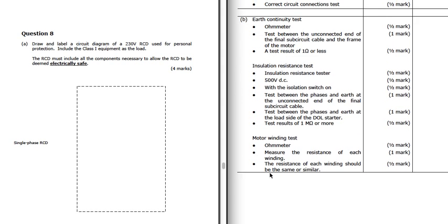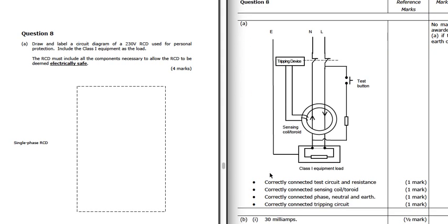Question 8, we're going to draw a 230 volt RCD used for personal protection, and we're on a class 1 equipment as the load, which we've got down here. We've got the toroid, we've got the phase conductor, live conductor and neutral conductor flowing through this, and then we've got the coil here, the sensing coil, and the tripping device. So if this sees an imbalance between the two, it will trip here and these will break these contacts.